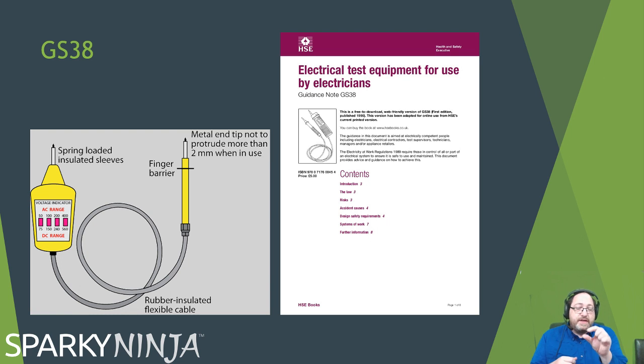To make sure that the exposed tips are 4 mm, preferably 2 mm of exposed metal, so we don't have any shorting out when we're in small control panels. To make sure that there's a fused lead or a high capacity resistor in the lead so that we don't have any arcs when we're holding the equipment, and just to make sure it's overall in satisfactory condition. But it's free information, so do make sure that you get it and update yourself on that so you haven't got to relearn it when you're on a course.